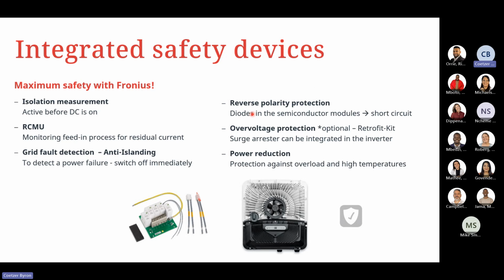We also have reverse polarity protection. So we've got diodes in the semiconductor of the modules, obviously to allow for the short circuit. Your over voltage protection. So again, this is an optional retrofit kit that's available. And then lastly is the power reduction. So this allows for protection against overloads as well as high temperatures.